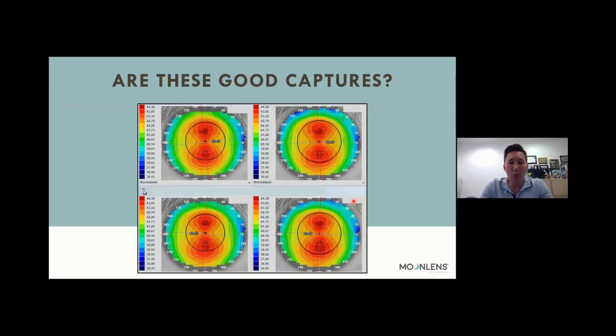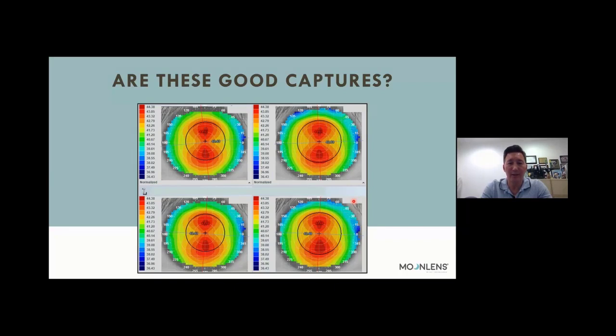It's not a bad idea to take multiple readings because you're dealing with a moving patient, a constantly moving eye, and tear film that's constantly moving. Here we see four topographies that look the same — we've got reproducible information, and that gives you much more confidence that you have accurate topography. Always take multiple maps; that assures you that you are looking at reproducible and hopefully accurate topography.